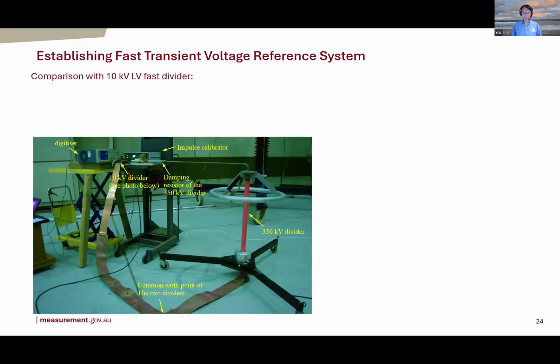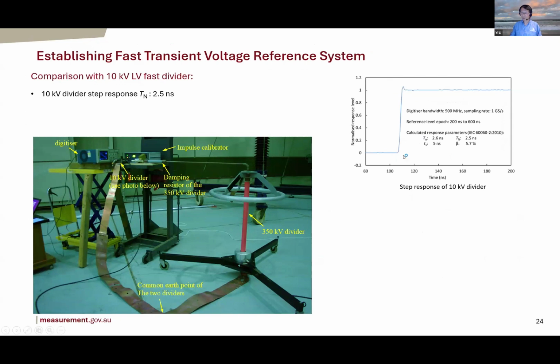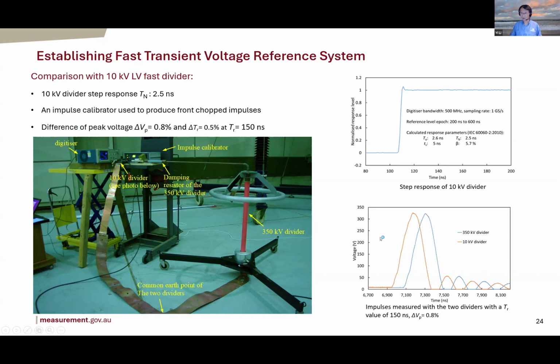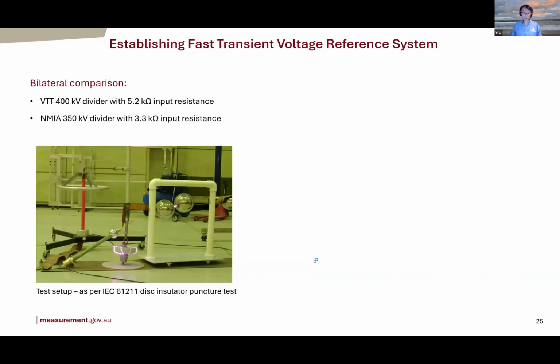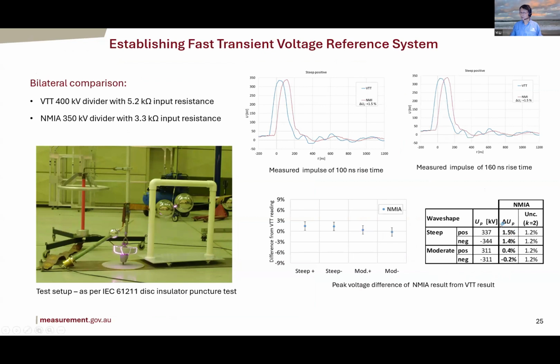And then with this extra work, you compare with the low voltage divider, which is 10 kilovolts, which is faster. And this is your fast transient divider, 350 kV. And this fast divider has a much faster step response, 2.5 nanoseconds. And then you compare these two at low voltage, you get almost the same voltage. Say the front is about 150 nanoseconds, you got a difference of 0.8%. And then we have also done comparisons in the fast transient field, so VTT, NMIA, and the different ones, for fast and slow. Fast is about 100 nanosecond rise, so slow is 160. It's just less than 2% difference.